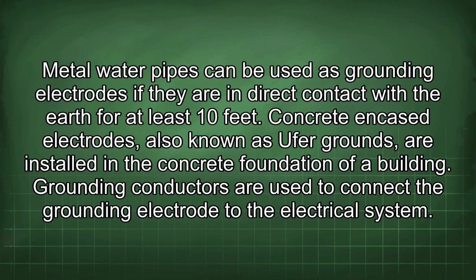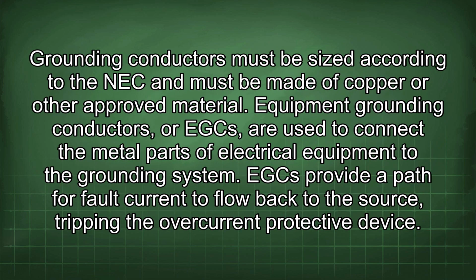Grounding conductors are used to connect the grounding electrode to the electrical system. Grounding conductors must be sized according to the NEC and must be made of copper or other approved material. Equipment grounding conductors, or EGCs, are used to connect the metal parts of electrical equipment to the grounding system. EGCs provide a path for fault current to flow back to the source, tripping the overcurrent protective device.